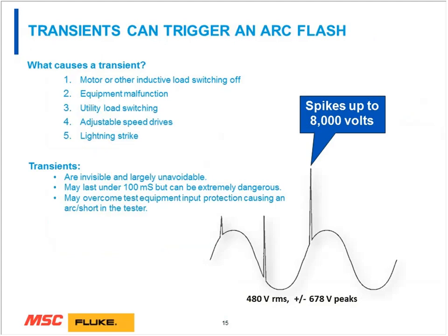The danger comes from transients. A transient happens when a motor or an inductive load is switched off, or from load switching by the utilities, or a lightning strike. That's where up to 8,000 volts or so could ride on top of the sine wave and find its way to you through the instrument that you're measuring. What's important is to look at category ratings. So let's take a look.